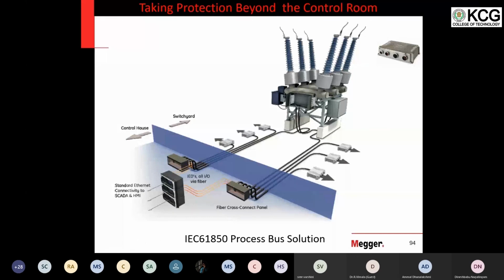Now let us see. Copper cable is eliminated because this is also fiber optic cable only. Copper terminates in this arrow mark. Second, relays are kept in the control room itself. It is not kept in the kiosk, in the switchyard. Therefore, in any failure, the operator can still operate from the relay, standing in front of it. He need not go to the switchyard.